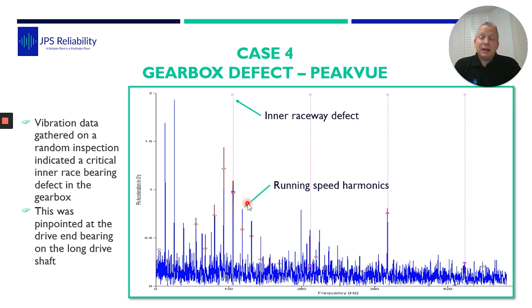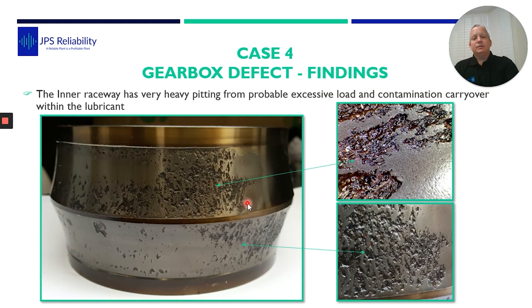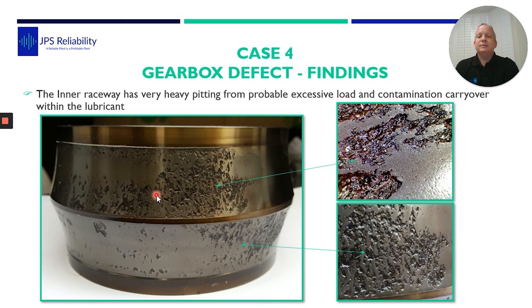Due to those findings, the classification was very urgent — they needed to schedule the gearbox removal before it gave short notice and functionally failed. Luckily they did remove the gearbox before it failed and affected system functionality.